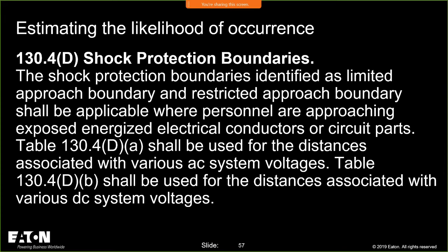understanding the shock, and the fact that we need to be able to recognize when we have a shock hazard, and we need to understand what is an exposed conductor and what is not, and steps we can take to reduce that likelihood. We may not be able to reduce the severity. I mean, if you come in contact with a 120 volt circuit, I could be killed because I'm not protected. But let alone a 480 volt and whatnot.